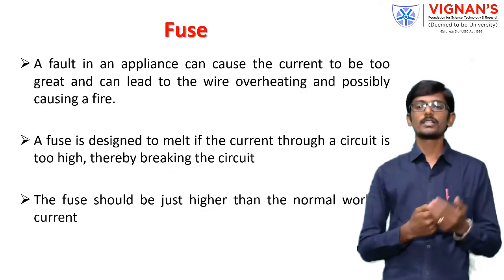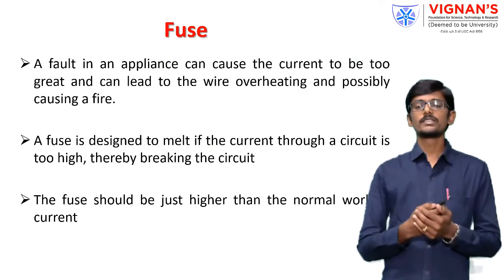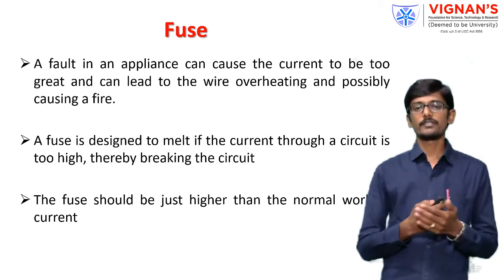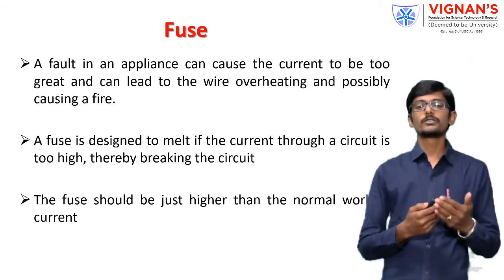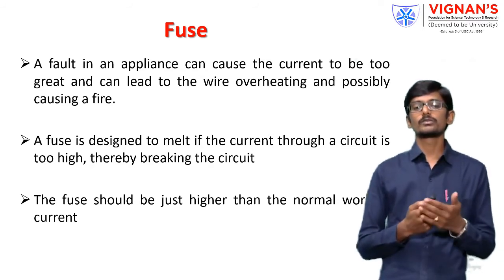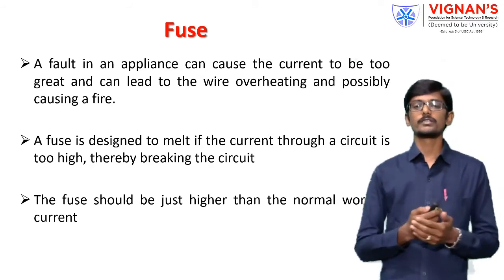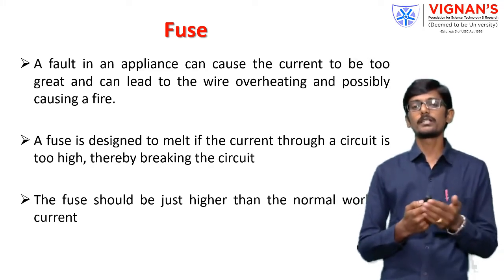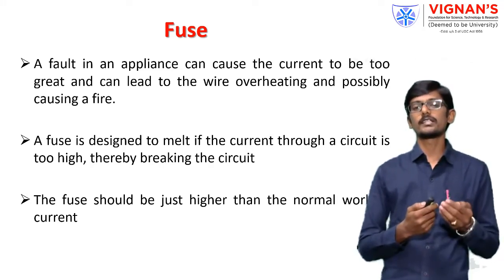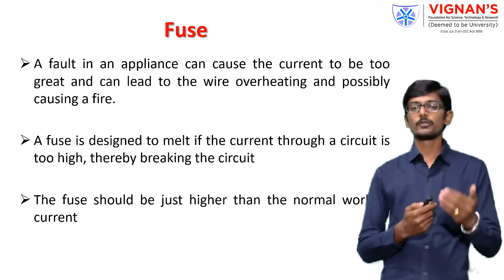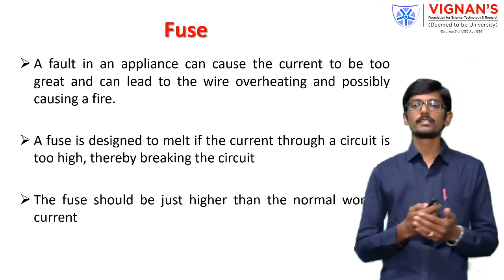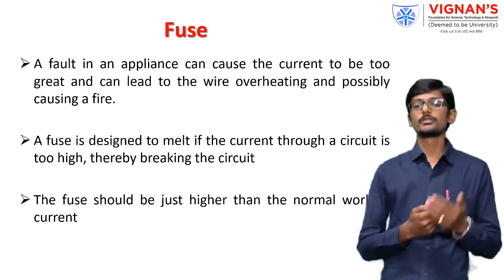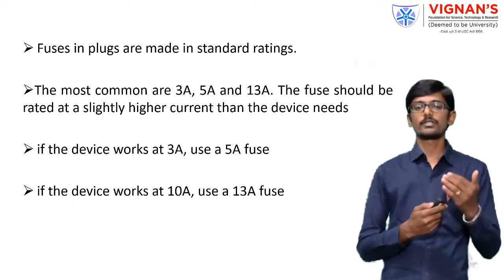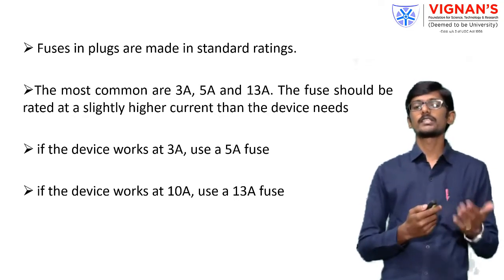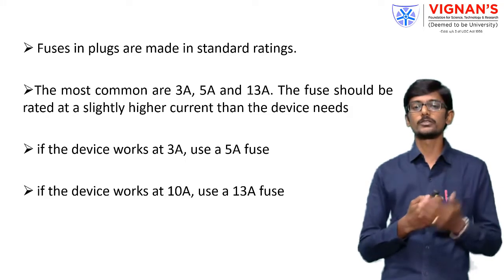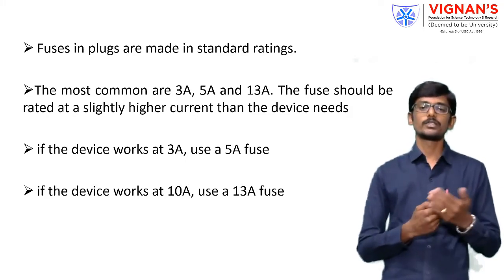A fuse is also a protective device which is used to protect electrical equipment under faulty conditions. The fuse is designed to melt if the current through the circuit is too high, thereby breaking the circuit. The fuse itself melts and burns when a fault current, or a current higher than the capacity of the equipment, flows in the circuit. The fuse will melt and break automatically due to the excessive heat. The common ratings of fuses are 3 amps, 5 amps and 13 amps, which are available in the market, and fuses up to 32 amps are also available.